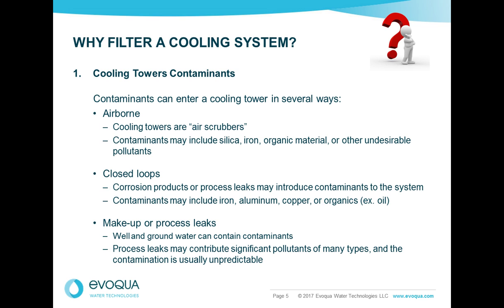Why filter a cooling water system? Contaminants enter the cooling system in a number of ways. The biggest issue is airborne contaminants. You've got dirt, dust. If it's a construction site or near a construction site, this is a real problem. You also have pollen and biological things like ragweed, spores, seeds, whatever. And your makeup water can contain some dirt, and this should be filtered out. You also can get process leaks getting into the system.